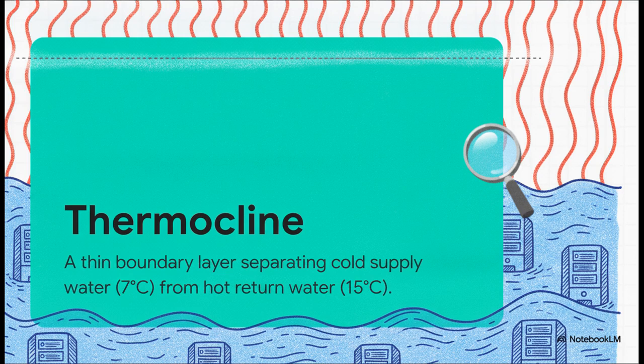If we peek inside one of these perfectly stratified water tanks, we'd find something called the thermocline. It's this razor-thin, totally invisible boundary layer. Below this invisible line, you have crisp, safe, 7 degree Celsius chilled water just waiting to be deployed. Above the line, you have 15 degree hot water returning from the server racks. You can basically think of the thermocline as a literal invisible shield. As long as that shield remains intact, the incredibly dense and hot server racks are completely protected.